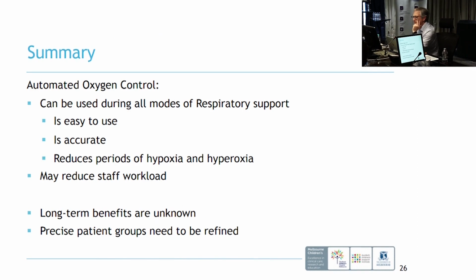So in summary, I think we have clinical experience and engineering experience that it can be used in all modes of respiratory support because it's a functional product and not a mode. It's actually pretty easy to set up, and we can show you here if you want to see how to do it. I think it is pretty accurate for what it's designed to do. Theoretically, it reduces staff workload. It may not reduce staff anxiety because, again, that's around training.